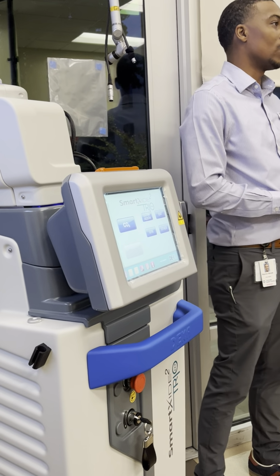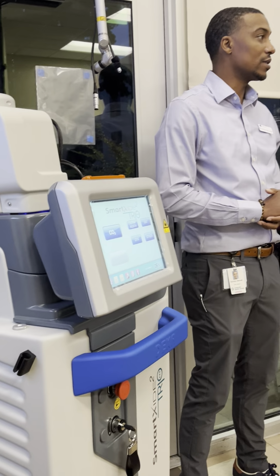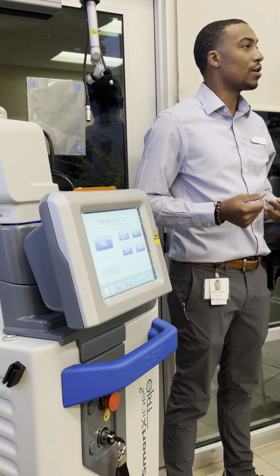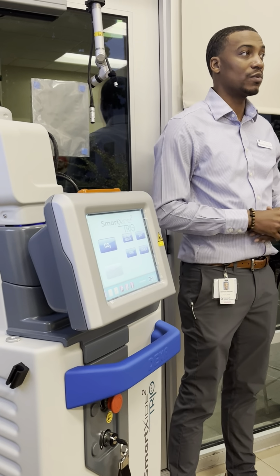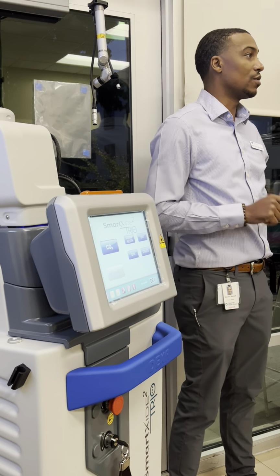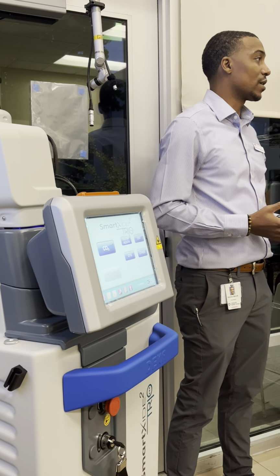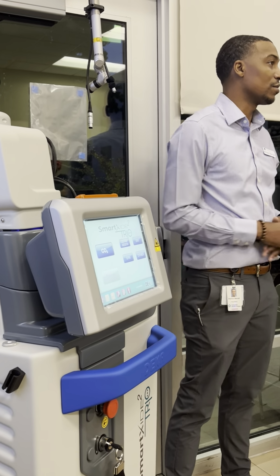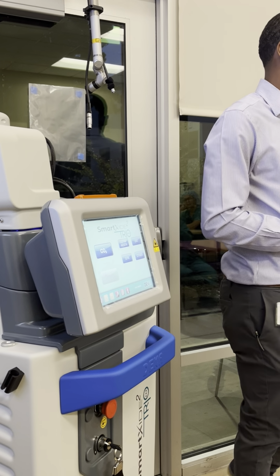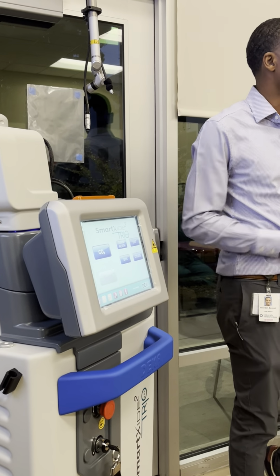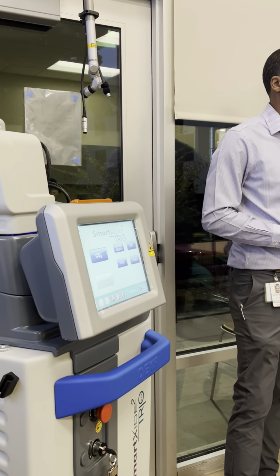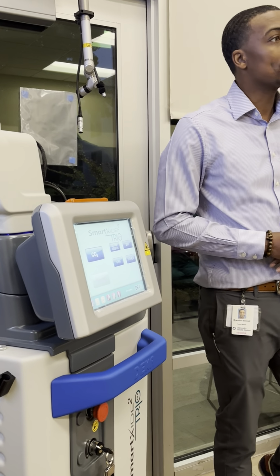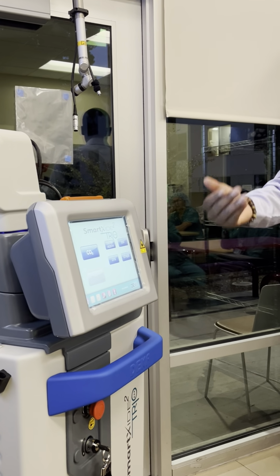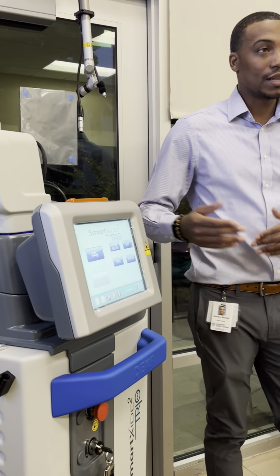That is the number one thing that happens with capital purchases. People are in a hurry, moving the machine back and forth between rooms, and they turn the machine on, plug it in, and think everything's okay. That can damage the servo and the motherboard of the machine, and it will not work anymore. You have to get the scanner and other parts replaced, which can be costly. Do you want me to get the micro manipulator? Please, just to show them what it physically looks like.